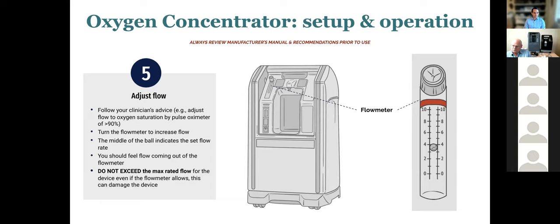So when adjusting the flow meter, always follow clinician's advice on the oxygen saturation goals for the patient, which should be checked with a pulse oximeter. There's a ball usually in these devices, adjusting them. The middle of that ball is going to indicate the flow. You should always feel flow coming out of the meter. It should be pretty obvious. If you're not, then there's something wrong.